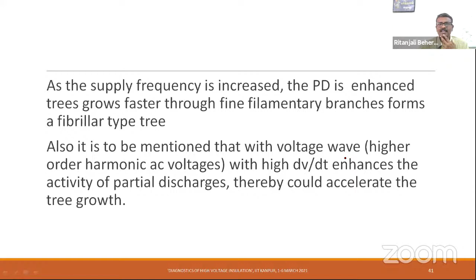Now the last part, treeing in nanocomposites. The tree initiation at the nanocomposites, LDPE alumina, can be observed here. For the first one, it is at around 10 kV. This is an unfilled PE, polyethylene, LDPE. The tree initiates at 10 kV. Whereas the tree initiates when the alumina as a filler is mixed with 1 weight percentage concentration, the tree starts at 11 kV.